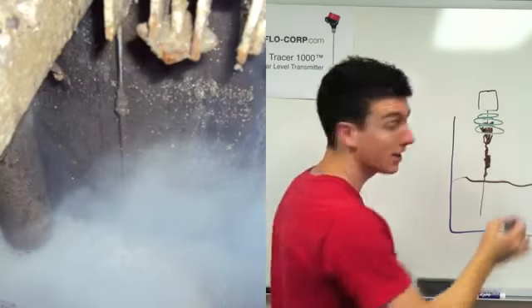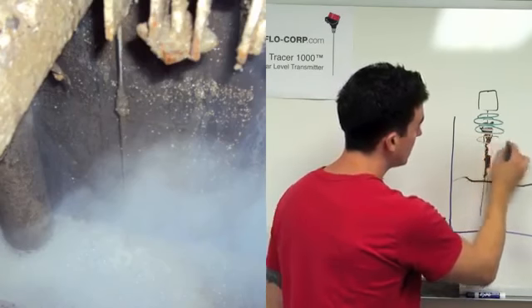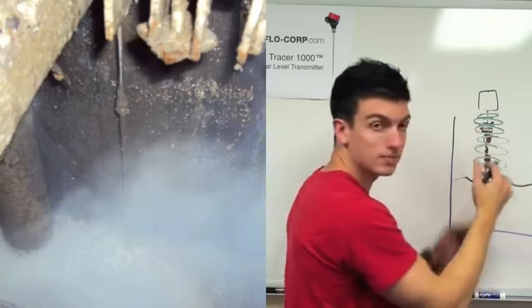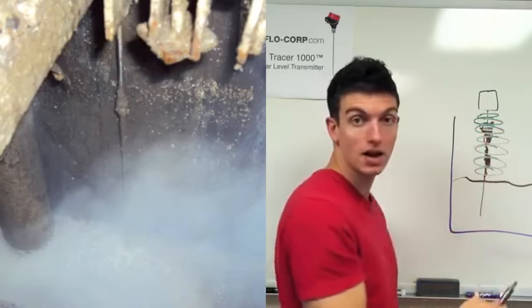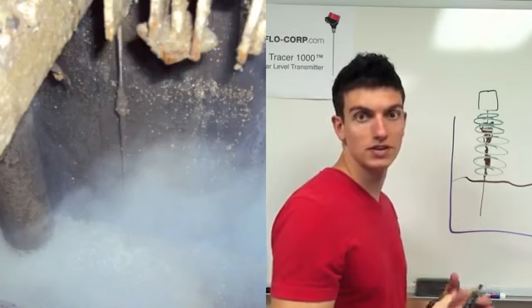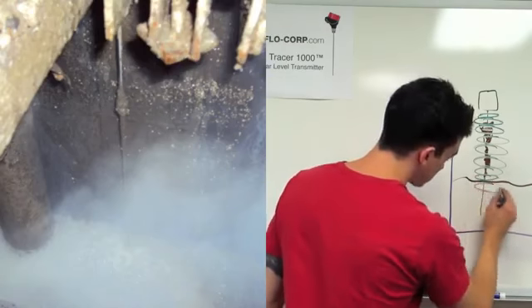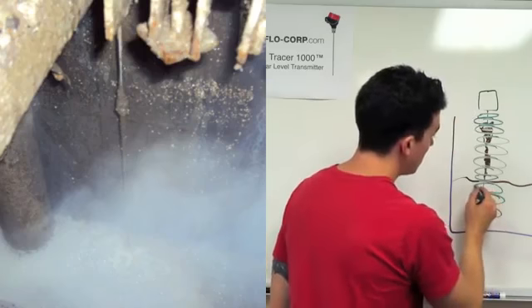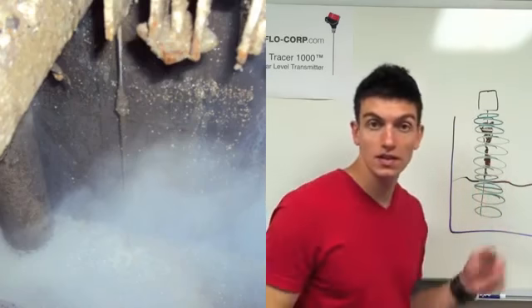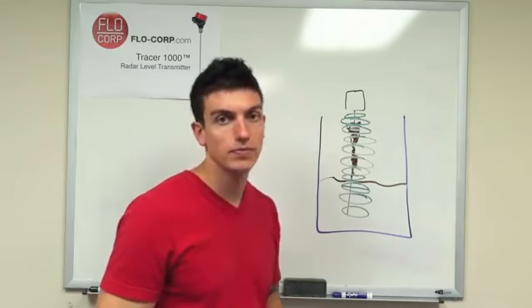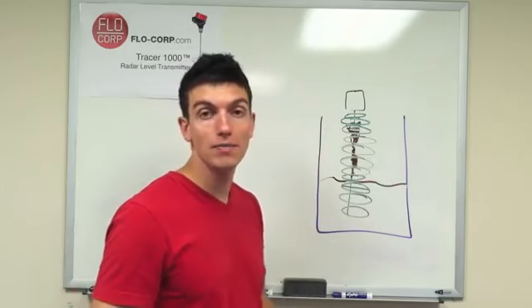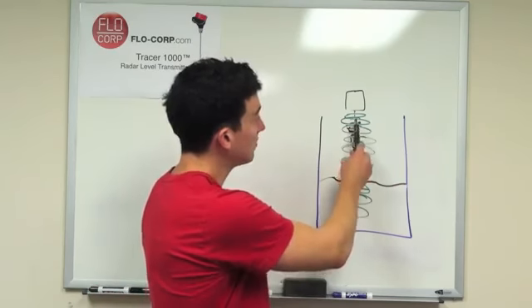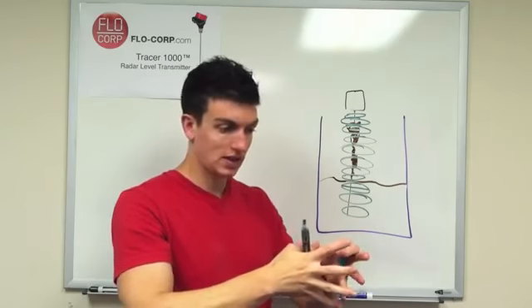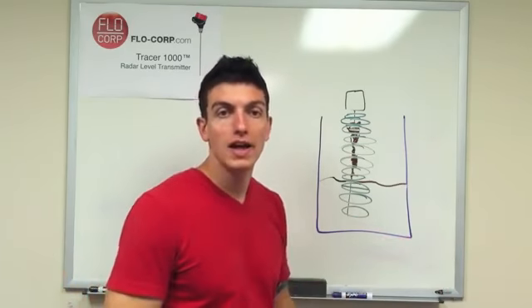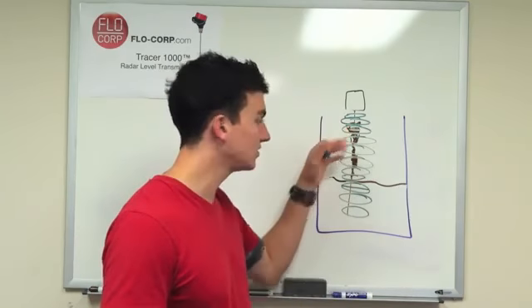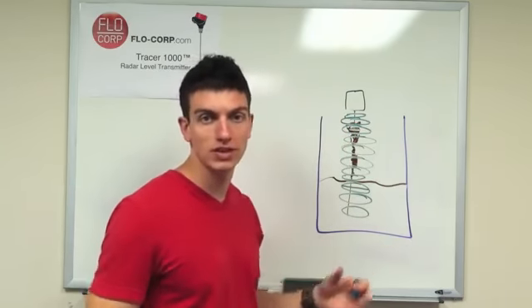All right, it starts measuring here, and it will take a measurement. It'll keep taking measurements, so it's recognizing there is some sort of substance here on the probe. When it finally gets into the level of the liquid, once again, it takes the accurate measurement. So emulsions are no problem because the microwaves extend in circular format out from the probe, and essentially it can factor out the emulsion because it realizes it's not the strongest and most complete signal.